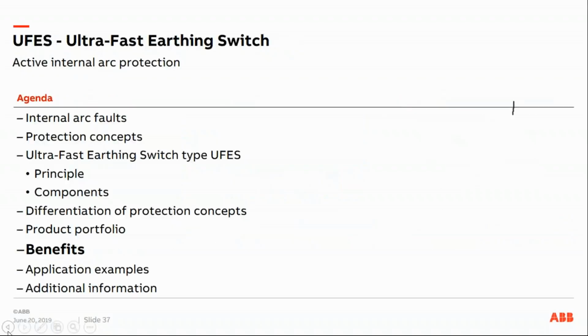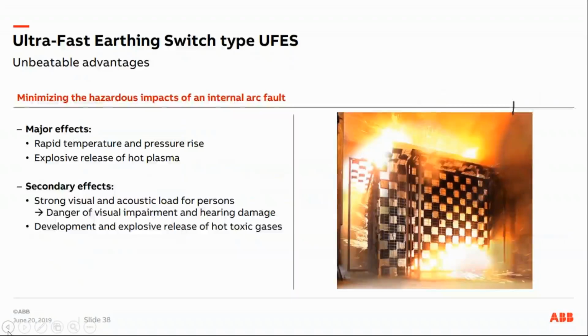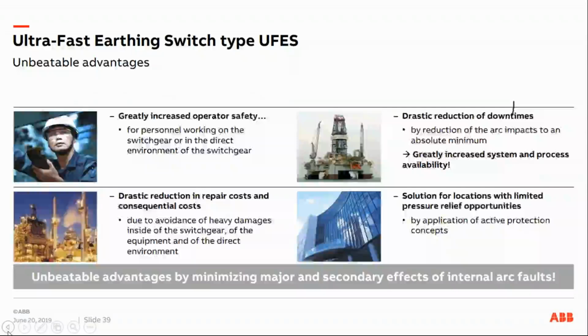Let's have a look at the benefits of the product. We've been talking about the impacts of an internal arc fault. One of the major effects is the rapid temperature and pressure rise and the release of hot plasma, and the secondary effects would be the visual and acoustic load for persons, such as in the first video, and the development of explosive hot toxic gases. So to sum it up, the UFES provides increased operator safety, reduces repair costs, reduces downtimes, and provides a solution for locations with limited pressure relief opportunities.